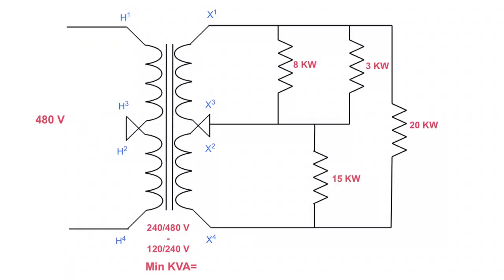In order to determine the minimum KVA of this transformer, we need to figure out the current of each branch. We have an 8-kilowatt load connected to 120 volts — you can see that because the load goes back on the neutral. So we take 8 kilowatts divided by 120 volts and we get 66.7 amps going through that branch. For the 3-kilowatt load connected to the 120-volt coil, 3 kilowatts divided by 120 volts gives me 25 amps.